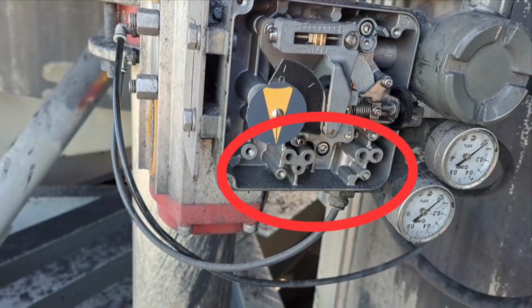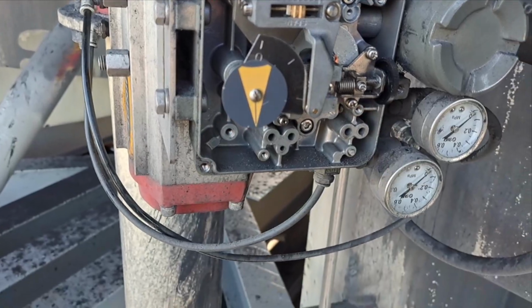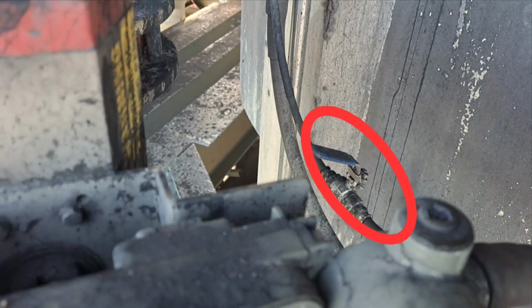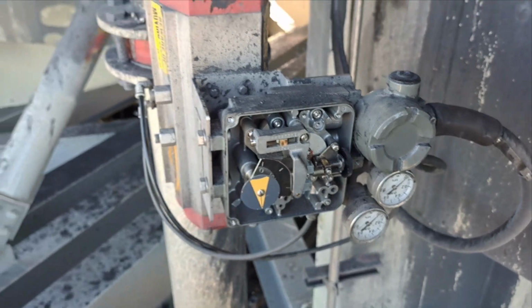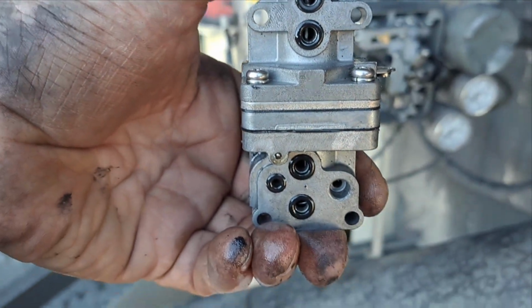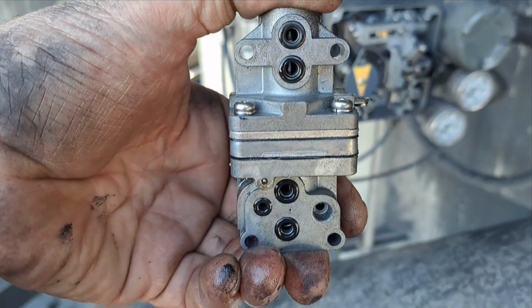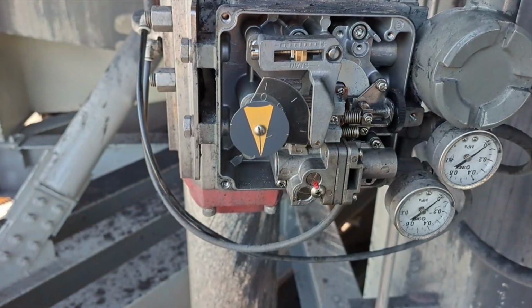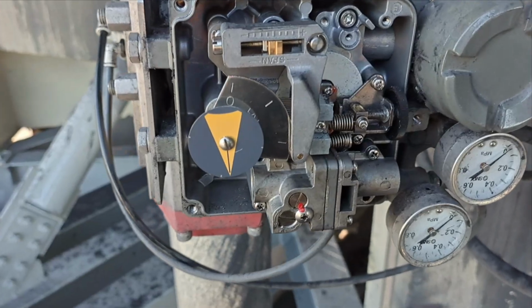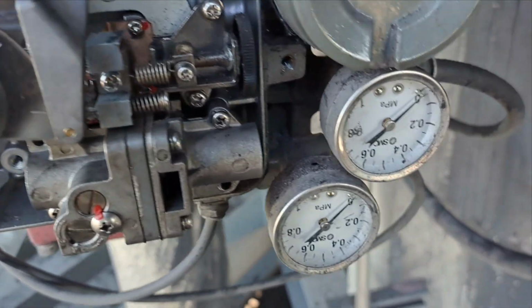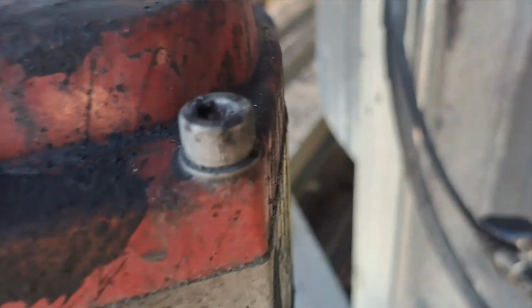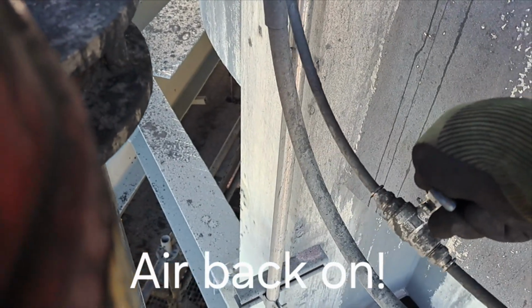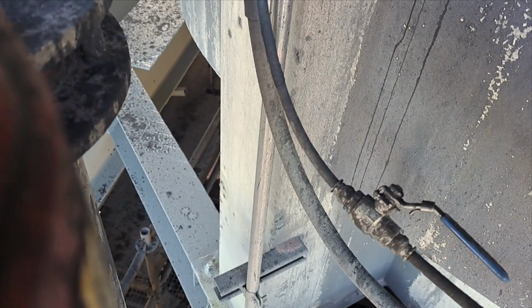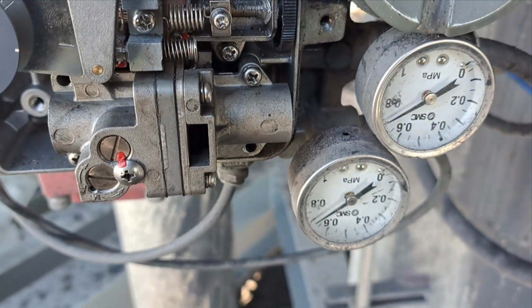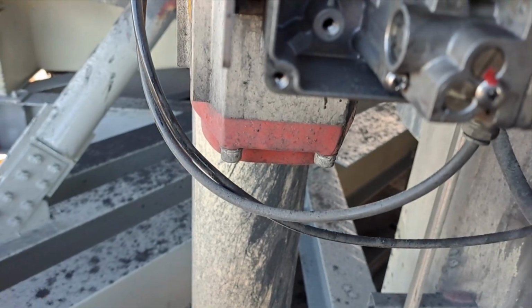I removed the pilot valve, but only after isolating the supply air and bleeding the line to release any stored energy. As you can see, there is a bit of water and moisture that came out of the pilot valve. I have replaced the faulty pilot valve with an overhauled and tested unit. Now I can restore the supply air to confirm my diagnosis. The valve is currently in the open position because the SCADA system output is set to 100% open.